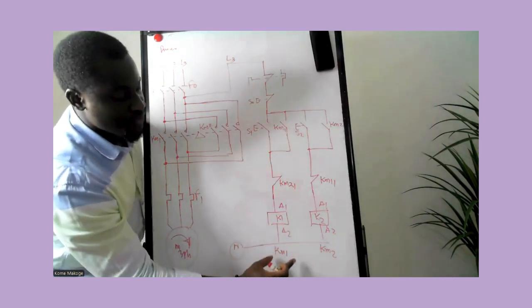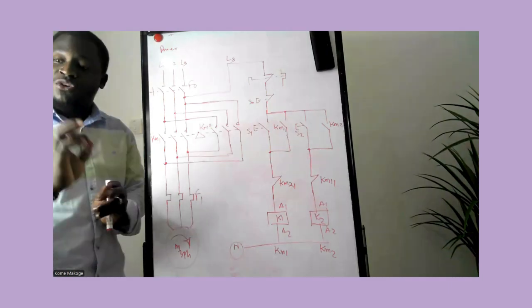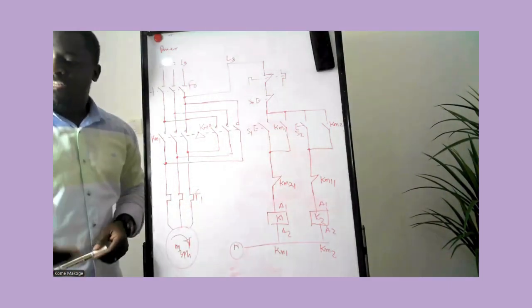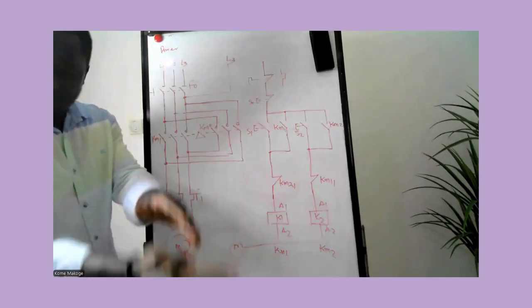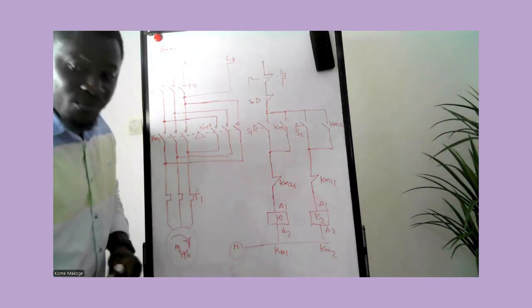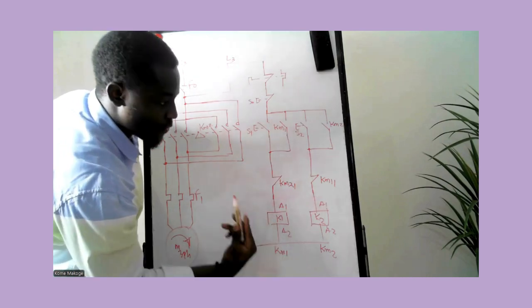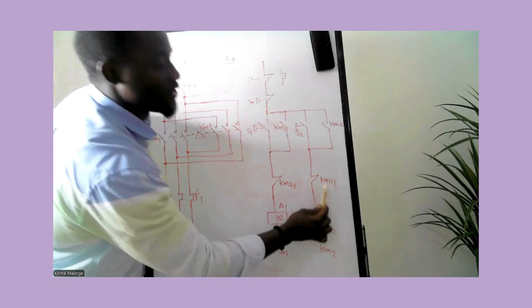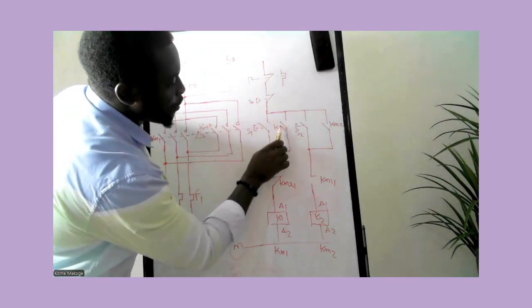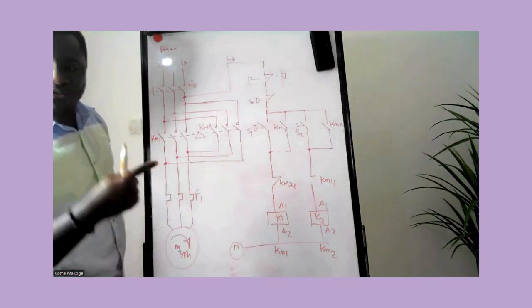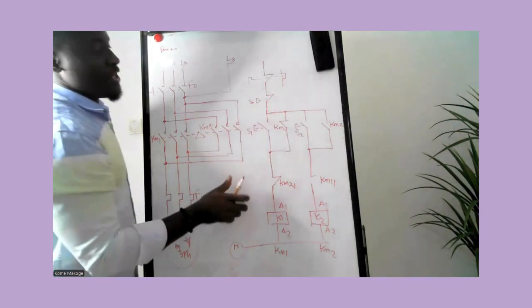The coil of contactor one — KM1 — will energize. When the coil is energized, or when sufficient voltage is applied, all associated contacts of that contactor are going to change their states: normally open contacts change to normally closed, and normally closed contacts change to normally open. So we now look at KM1 — this contact is going to open. And looking up here, we see another KM1 contact which is normally open — it now closes.